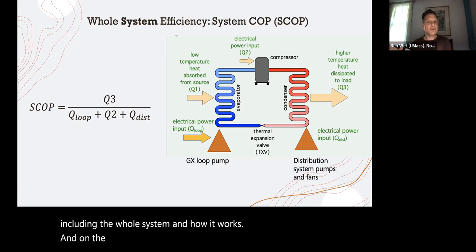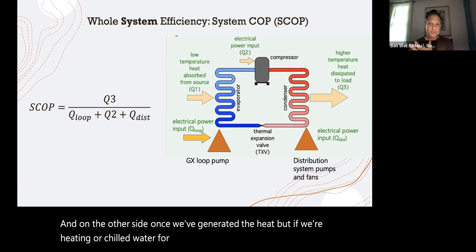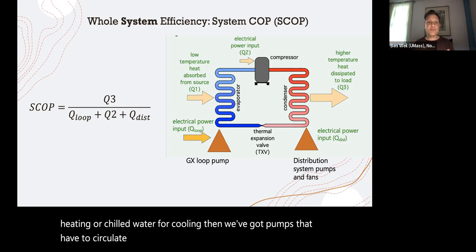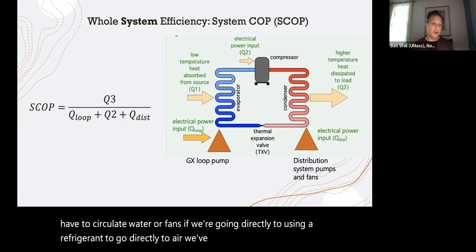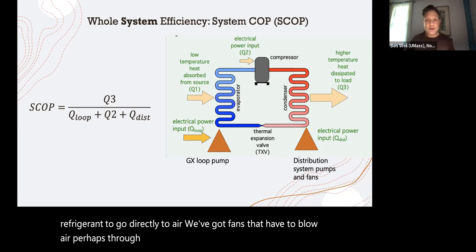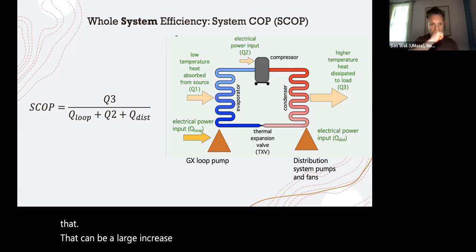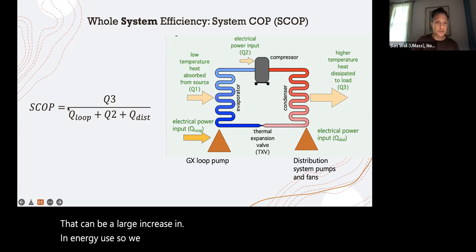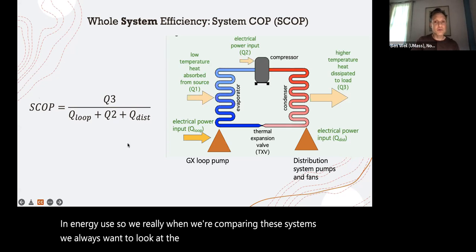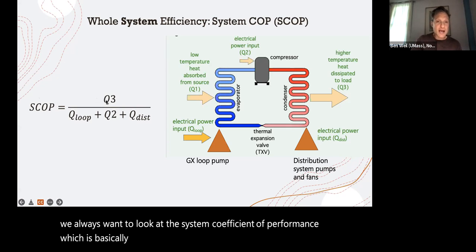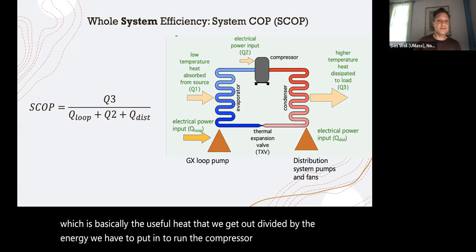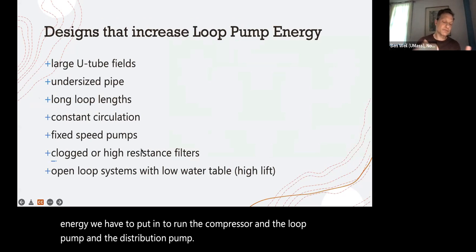And on the other side, once we've generated the heat, if we're heating, or chilled water for cooling, then we've got pumps that have to circulate water, or fans, if we're going directly to using a refrigerant to go directly to air, we've got fans that have to blow air, perhaps through ducts. And depending on how we've designed that, that can be a large increase in energy use. So when we're comparing these systems, we always want to look at the system coefficient of performance, which is basically the useful heat that we get out divided by the energy we have to put in to run the compressor and the loop pump and the distribution pump or fans.